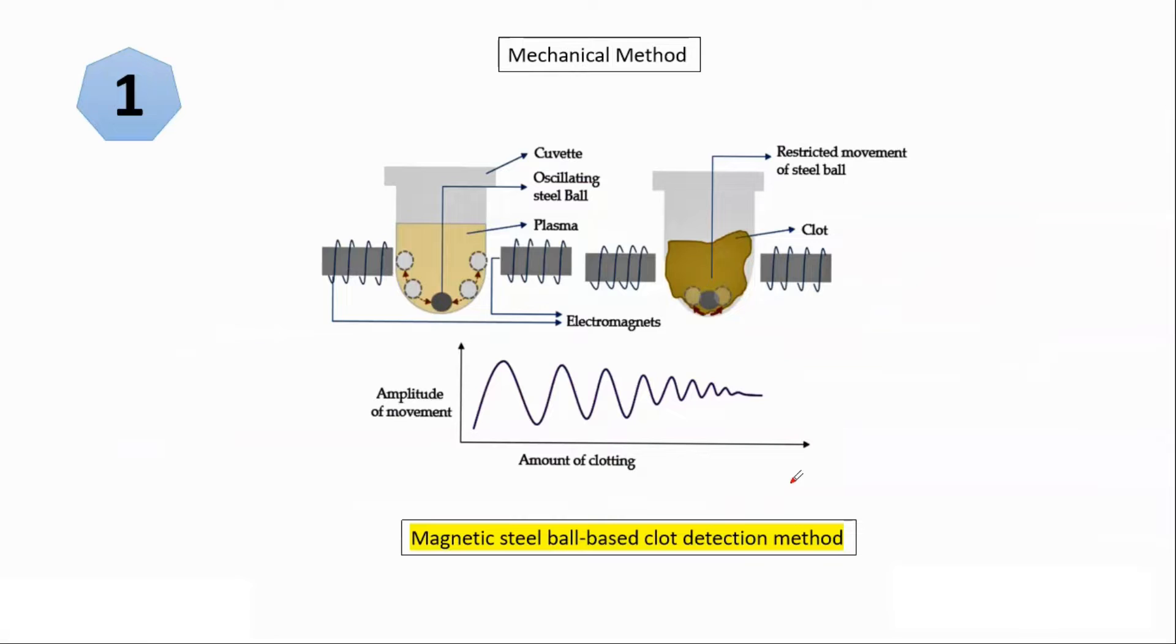So first method, first and most common method which is widely used in automated instrument for coagulation studies. So this is a cuvette or vessel in which we have a stainless steel ball. Here is a magnet, this is the magnet. Here also is the magnet. The principle here is at one point of time this magnet is activated.